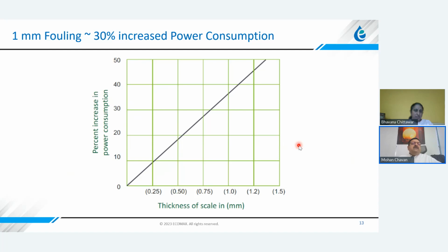This is another simple graph which shows how the scaling thickness affects the power consumption. So you can see the impact of the scaling here. So 1 millimeter of fouling or scaling can increase the specific power consumption by almost about 30%. So it's all the more important to avoid this fouling or scaling in the condenser tubes.